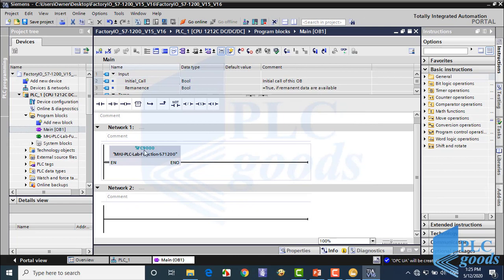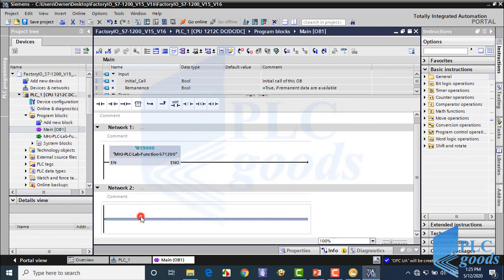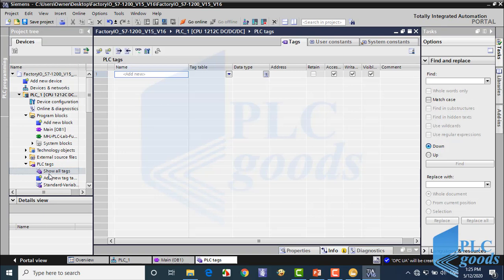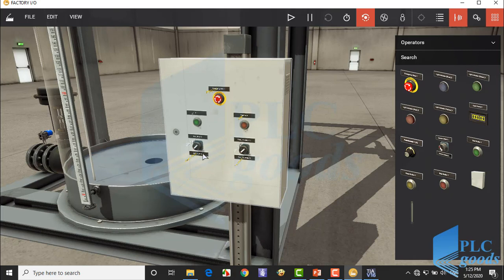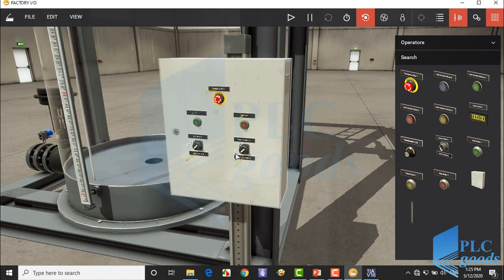Now let's start programming. First let me define my PLC input output tags. Here we have 5 equipment which must be connected to PLC inputs. Pay attention, each selector has 2 modes and will need 2 PLC inputs. So based on this control box, we need 7 PLC inputs.